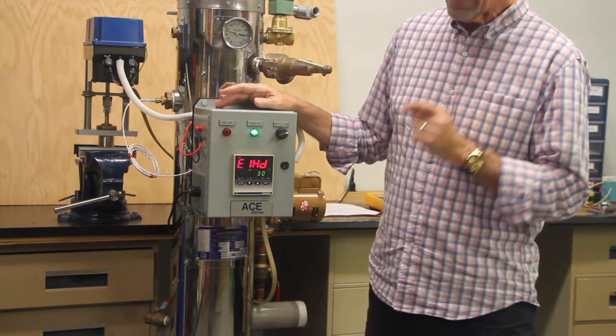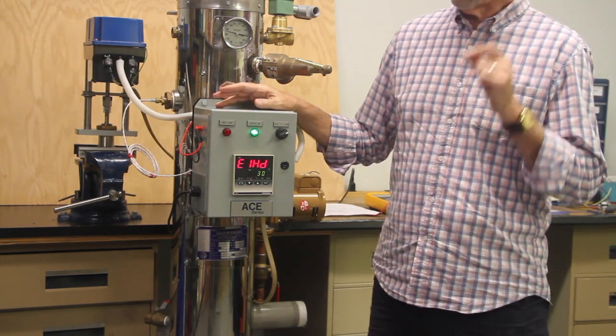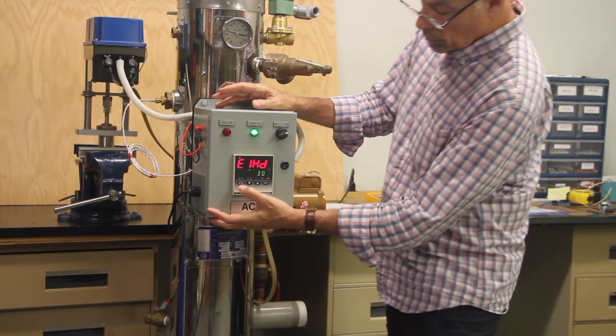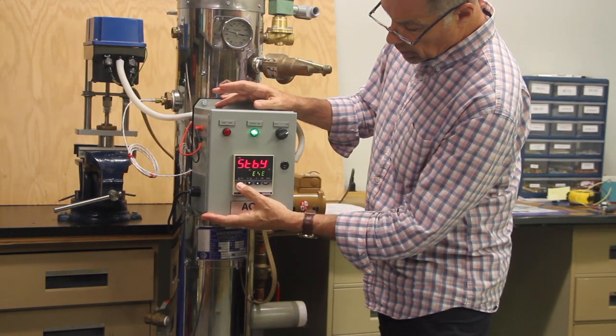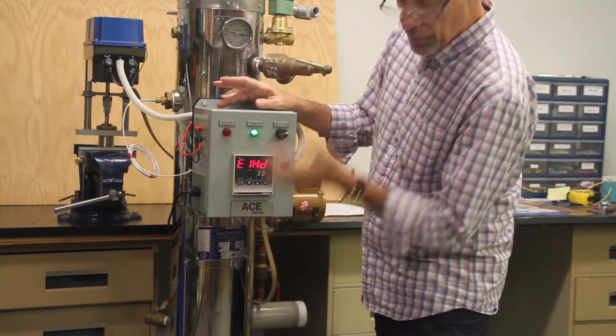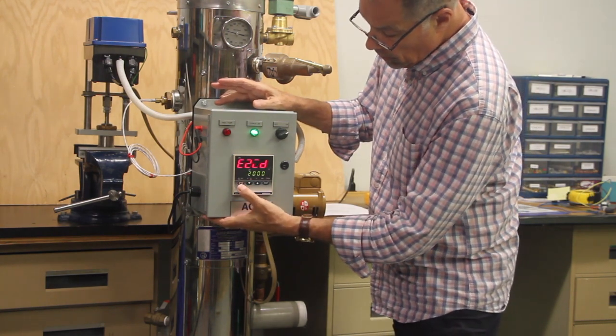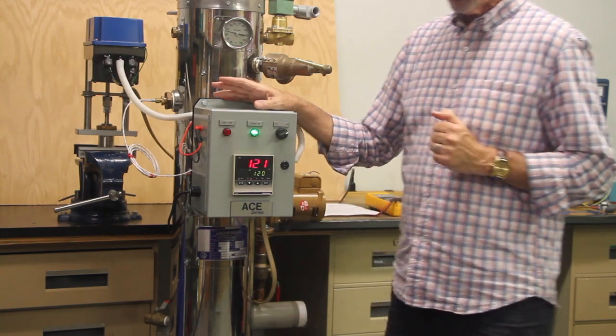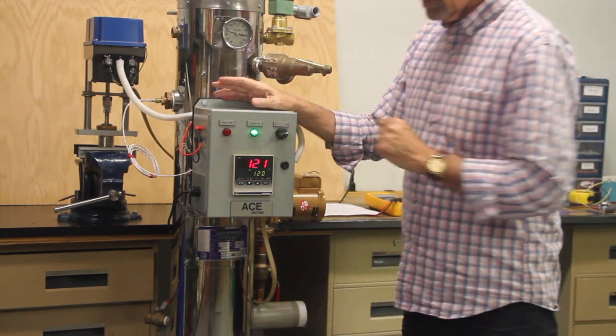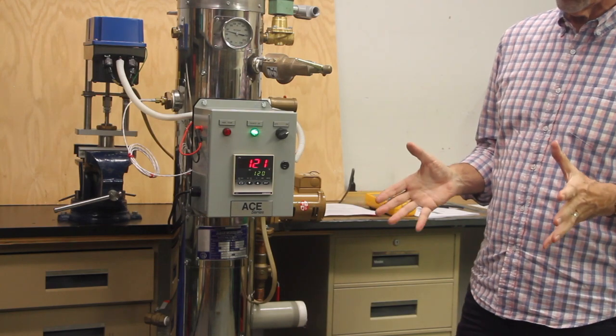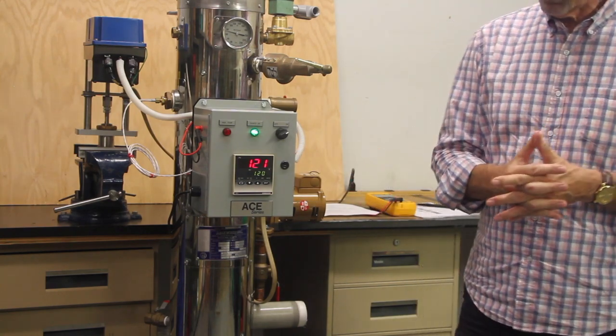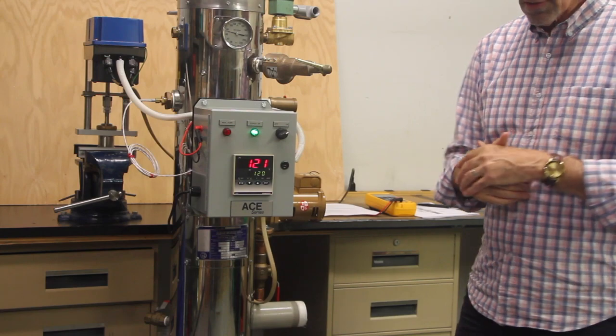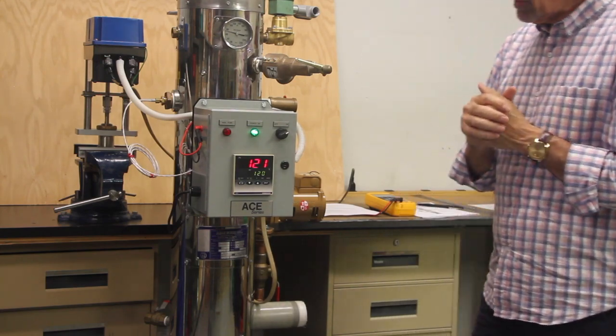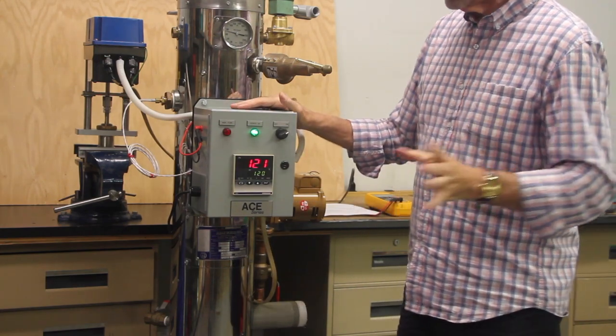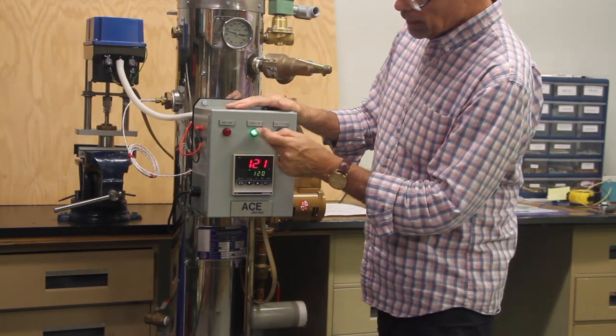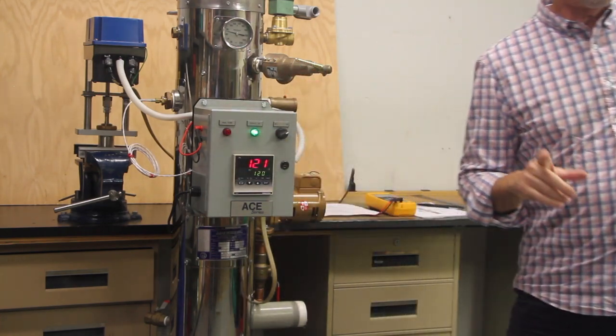It says E1HD. It's an emergency dump for high differential. If you notice, we're set at 30 degrees for the E1HD. So our water temperature is 120. This heater will trip and shut itself down at 150, 30 degrees over the set point. We can change that. We can lower that to 20. We can raise it. It depends on the application. And we're going to demonstrate later how this will trip. And the green light will go to red.